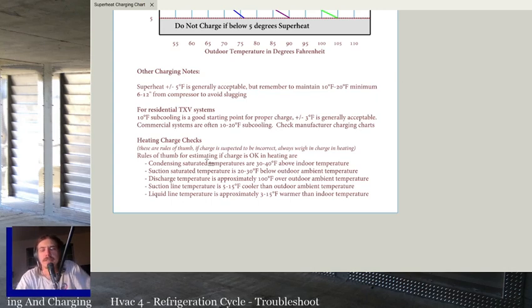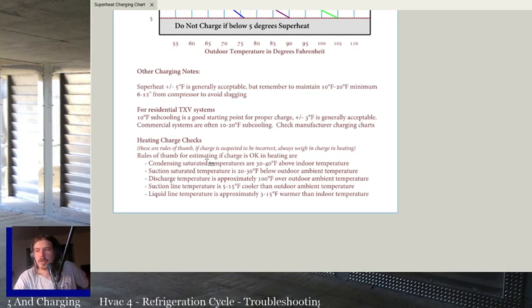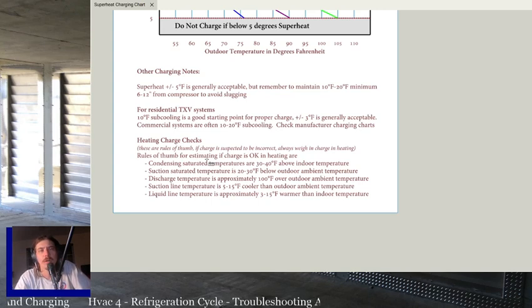Heating charge checks. This is always a weird one. I know a lot of guys won't even bother trying to check charge in heating. You should never actually charge the system as if it's going to be finally charged in heating mode. But you can get a good idea whether or not you are low on refrigerant when the heat pump's operating in heating. So if you can't run it in cooling to check the charge, these are some rules of thumb that you can use to say, okay, does the charge look okay, or does it look like I got a leak? Am I out here because the electric heat is running all the time because the charge is messed up, or something else going on?